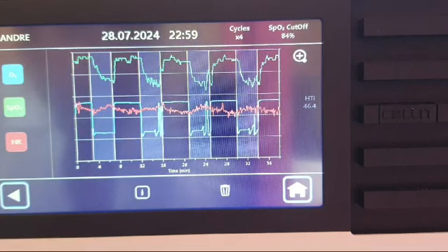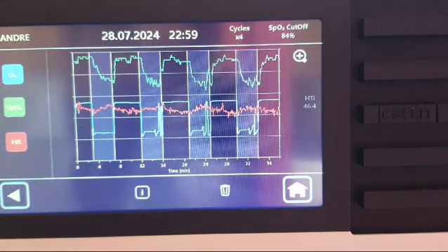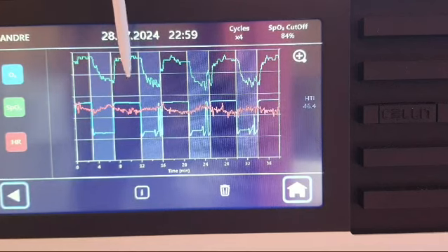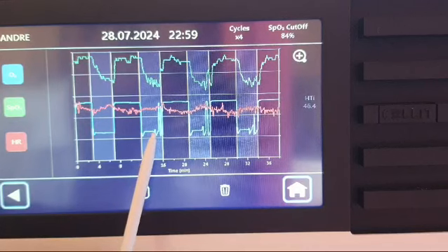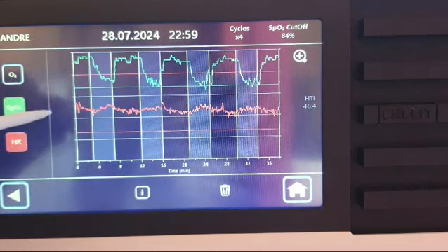As a very initial analysis of this breathing session, for example, what we can observe is that in this session, the user actually went below what was supposed to be the cutoff. And this is an interesting example because you can see that in the third cycle, so the second cycle of hypoxia, the machine had to bump up the O2 percentage back up because the cutoff level was broken. And you can see that here.